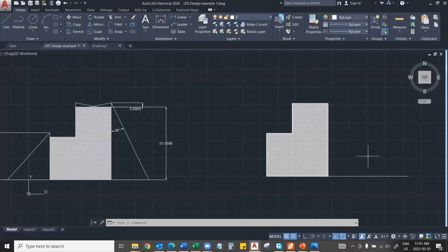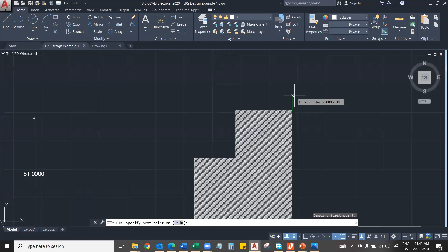So if it's acceptable, let's say you have 1 meter, because 3 meters is almost like a floor level, right? So there are practical limitations as well. You cannot simply put 4 meter, 5 meter, 6 meter lightning arresters. You would need proper mounting structures to accommodate that, or else you have to try to minimize these additional burdens. You first have to do particular attempts.